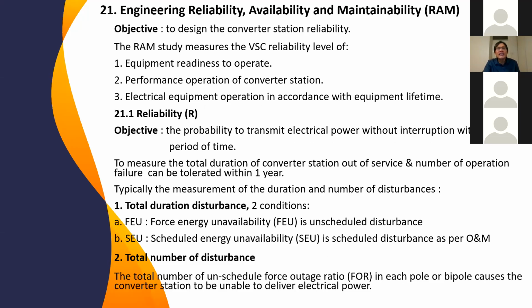RAM, the objective is to design the converter station to perform better. What is the RAM here? Reliability, the objective is the probability of transmitting electrical power without interruption within a certain period of time. Typically, measurement of the duration and number of disturbances can be divided into two. One, total duration of disturbance with two conditions, forced energy unavailability or scheduled energy unavailability. Or the second one, we measure through the number of disturbances, either each pole or bipole within 1 year of operation.